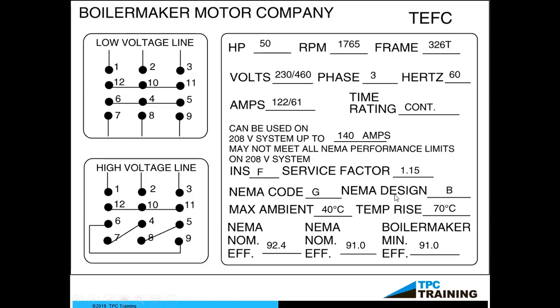It is a NEMA Design B motor. So the NEMA design gives us great information about the torque characteristics of the motor. And a Design B motor has normal starting torque, normal running torque. So that's good. If it happened to be a Design D motor, then we would have high starting torque and high running torque like a winch. But this is your basic three-phase induction motor we're looking at. So, should be fairly easy to understand: normal starting torque, normal running torque.